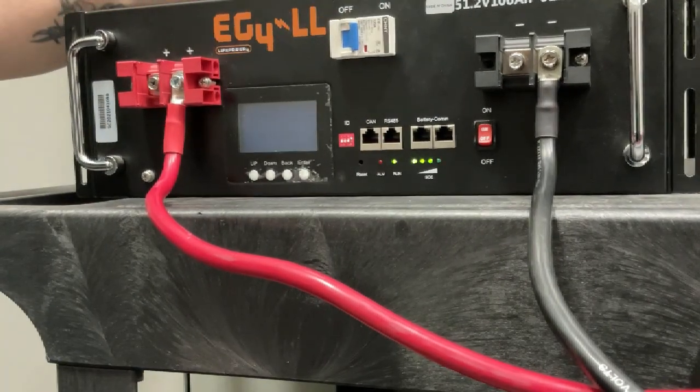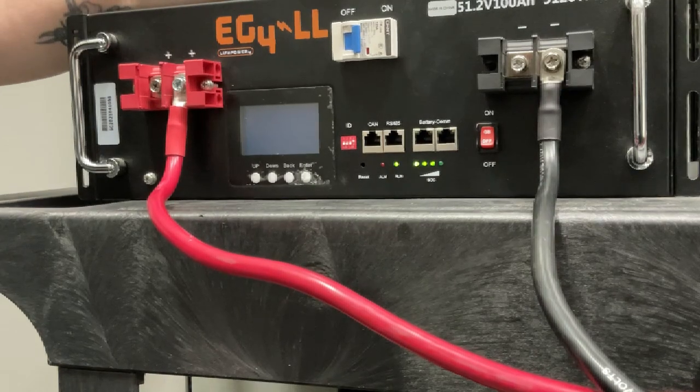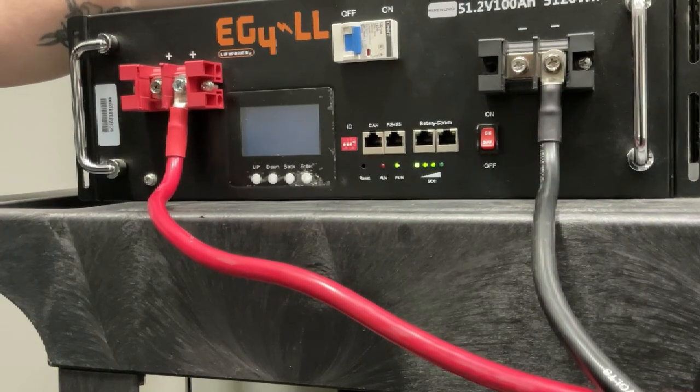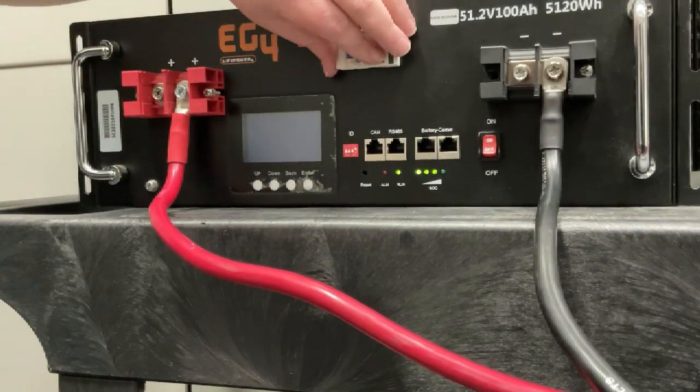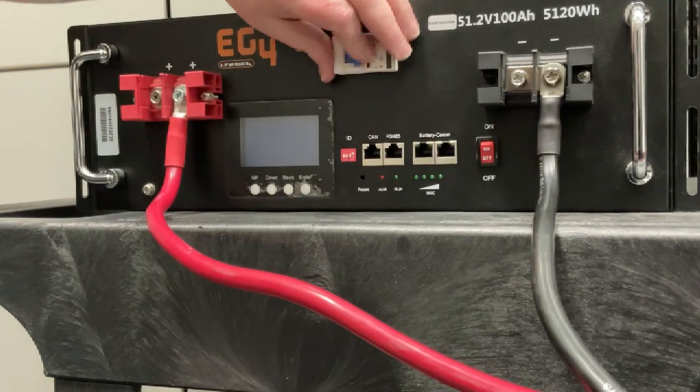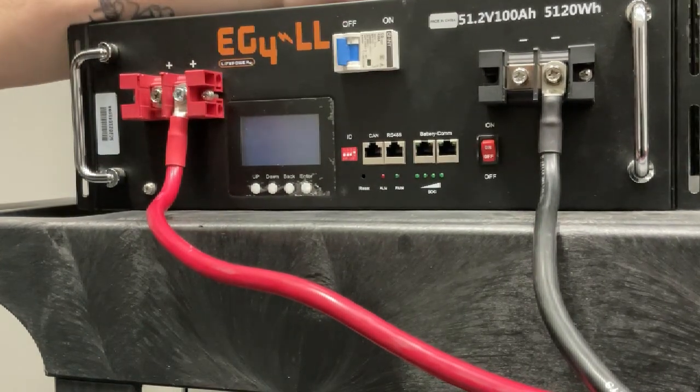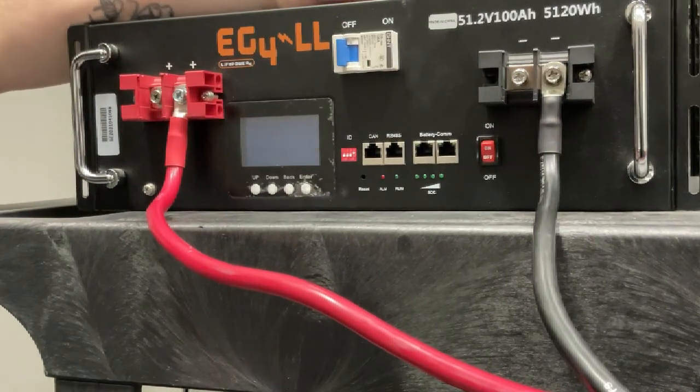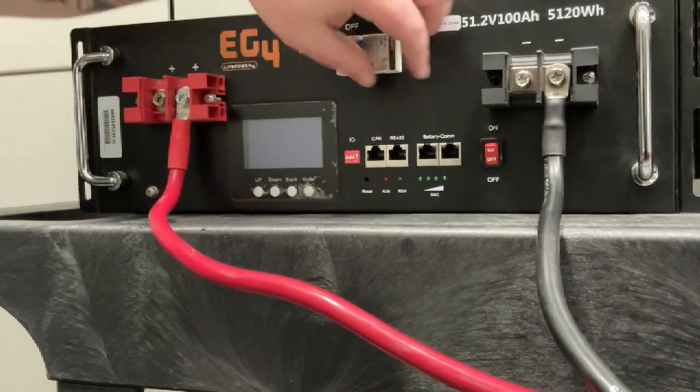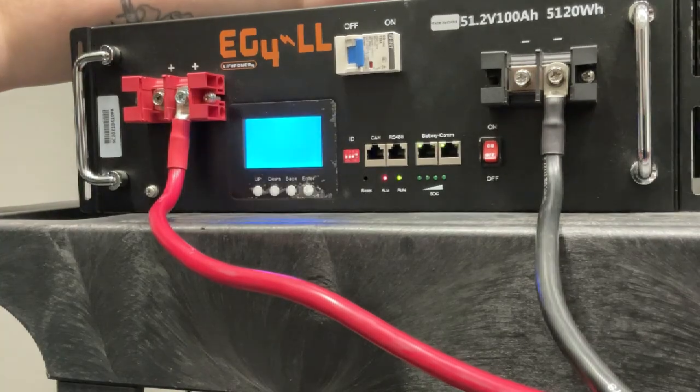Now, because our battery was already on whenever we had to change our dip switch setting, in order for the battery to realize the new dip switch, we actually need to completely power cycle our battery. So once you've switched your battery off and you've let it set for a moment, go ahead and flip that back on.